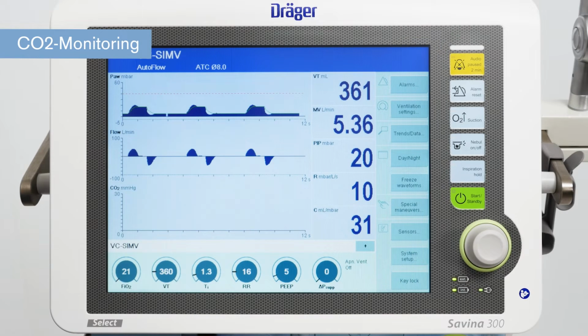If CO2 monitoring is used, check the CO2 0 indication. The prerequisite for that is a clean CO2 sensor placed on the cuvette. Use a clean or a new cuvette. An at least 3-minute warm-up phase for the CO2 sensor has to elapse.